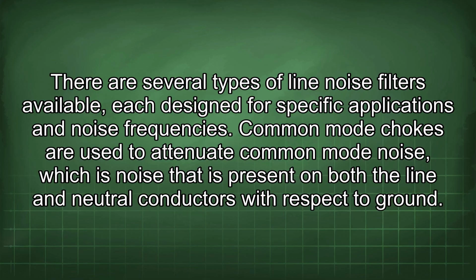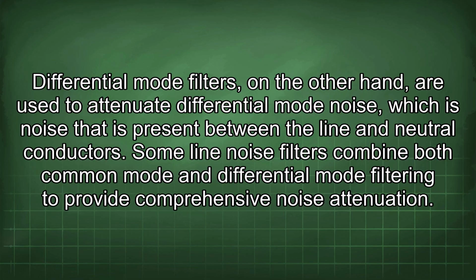Common mode chokes are used to attenuate common mode noise, which is noise that is present on both the line and neutral conductors with respect to ground. Differential mode filters, on the other hand, are used to attenuate differential mode noise, which is noise that is present between the line and neutral conductors. Some line noise filters combine both common mode and differential mode filtering to provide comprehensive noise attenuation.